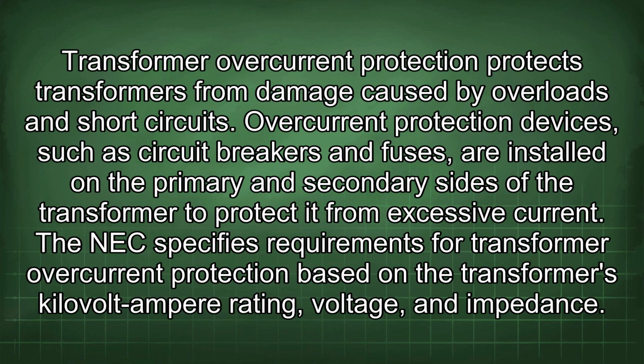Transformer overcurrent protection protects transformers from damage caused by overloads and short circuits. Overcurrent protection devices, such as circuit breakers and fuses, are installed on the primary and secondary sides of the transformer to protect it from excessive current. The NEC specifies requirements for transformer overcurrent protection based on the transformer's kilovolt-ampere rating, voltage, and impedance.